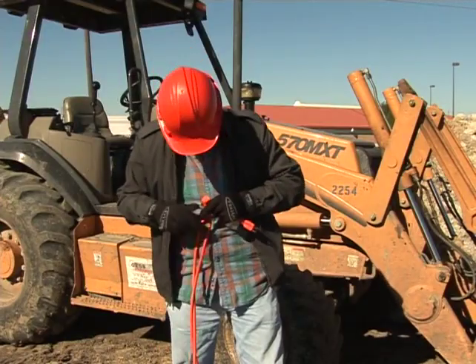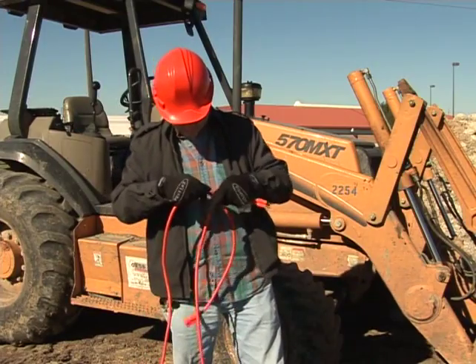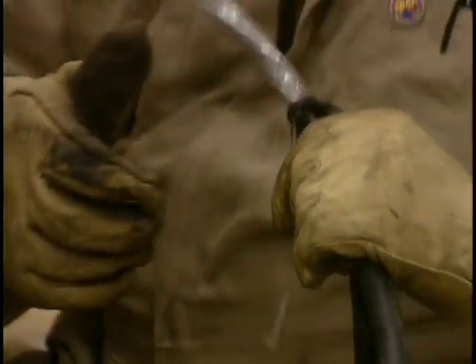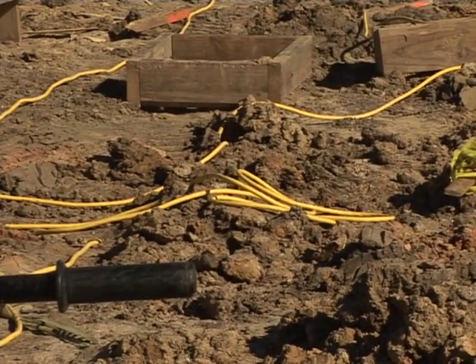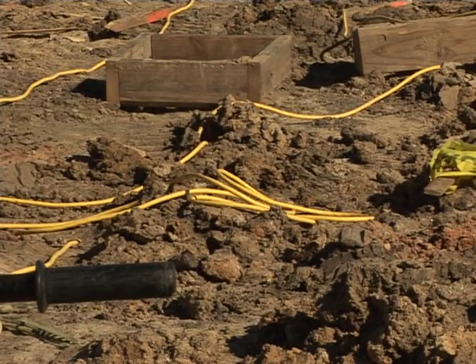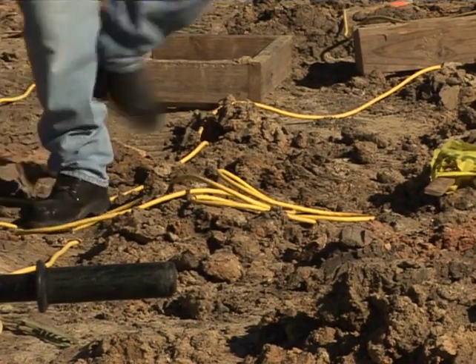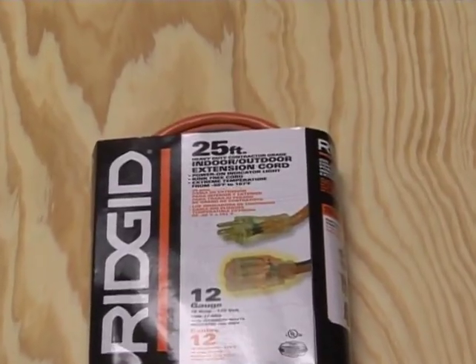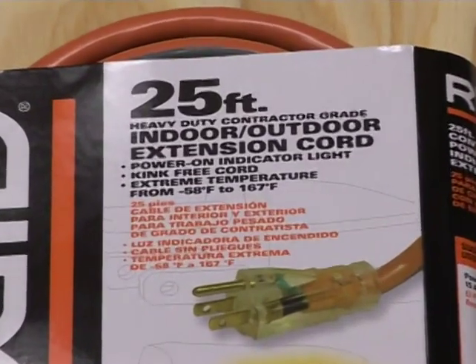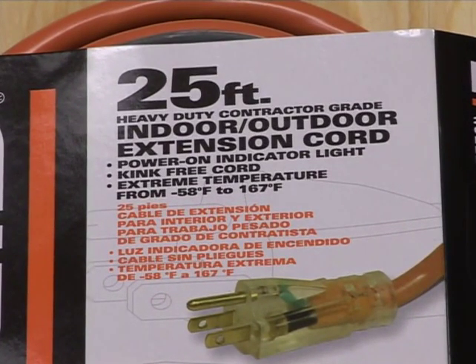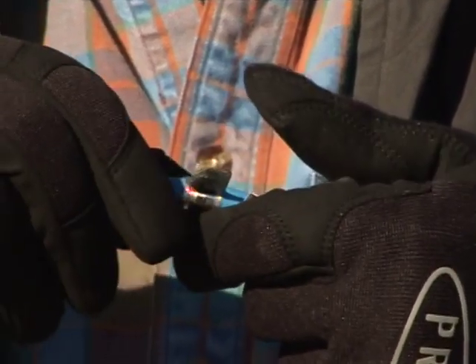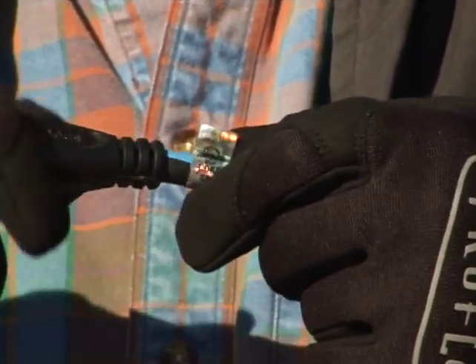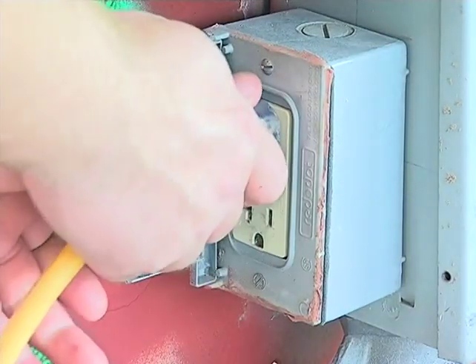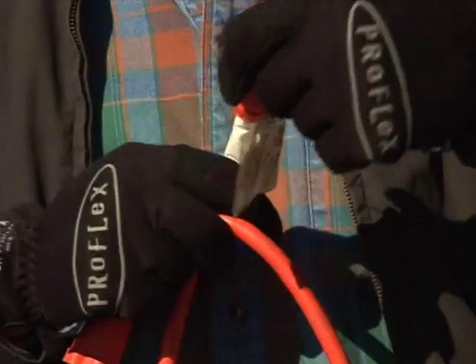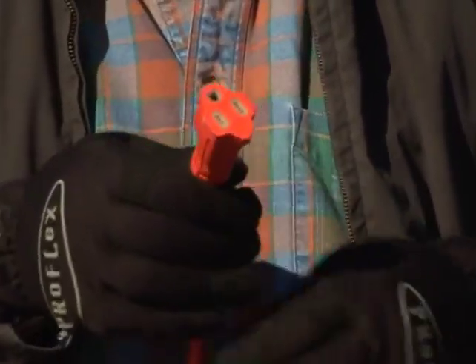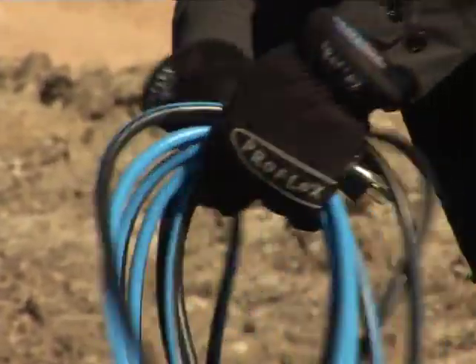Before use, inspect cords or tools for worn insulation or exposed wires. Never remove ground prongs, faceplates, or insulation from wires. Normal wear and tear on extension and flexible cords at the worksite can loosen or expose wires, creating hazardous conditions. Only use factory-assembled cord sets, properly rated, that are 3-wire type and made for hard or extra hard usage. Use only cords, connection devices, and fittings that are equipped with strain relief. When unplugging cords, pull on the plug, not on the cords. Continually audit and inspect cords on site. Remove unsafe cords immediately.